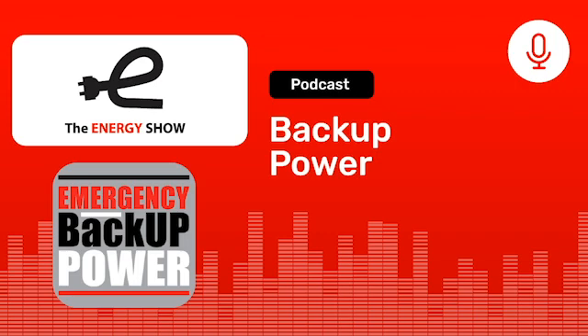So, talked about gas. Now let's talk about the cool new thing, which is what people are really interested in, which is solar with battery backup. It's definitely the future. It's ideal to install, say, a 7.5 kilowatt system with a 7.5 kilowatt inverter. Maybe you have 8 or 9 kilowatts of solar panels on the roof, and then you can have a critical load subpanel that's connected to that inverter and the batteries that'll just run what you need in the house.